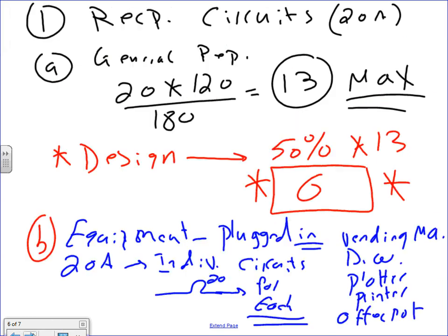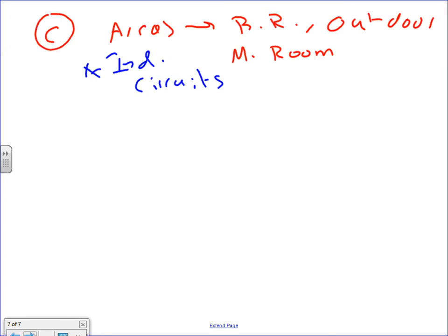All right, let me go to lights. Any questions, guys, before I move to lights? Receptacles are easy. So moving forward, how many receptacles within the circuit? 6 receptacles. Anywhere in a commercial building, no more than 6. Individual circuits for individual equipment when we know where they're located. Certain areas, give them a circuit. Even the bathrooms, for example, we have 2 bathrooms. How many receptacles in each one of them? 1 in each. There are 2 receptacles, they're going to have 1 circuit. Yeah, good idea. Even though there are 2 receptacles, having 1 circuit. Does that make sense?